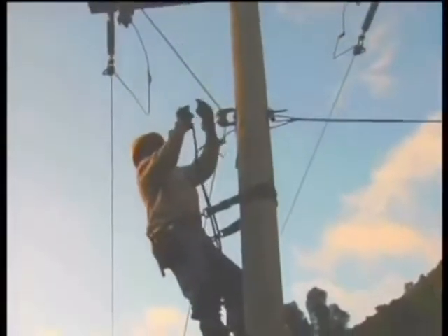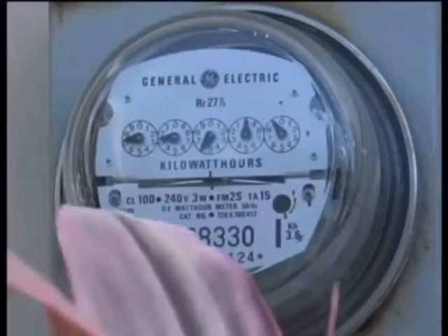It will lower efficiencies, and it would actually cause the motor to burn in instances, because now you're drawing more current than the equipment was actually designed for. So when you use a 60 Hertz appliance on the JPSCo's 50 Hertz grid, this is what could happen. What you're using is losing efficiencies. And it's nice to talk about a particular piece of equipment like a refrigerator. You would actually be losing about 12.5% efficiency on the refrigerator, right?